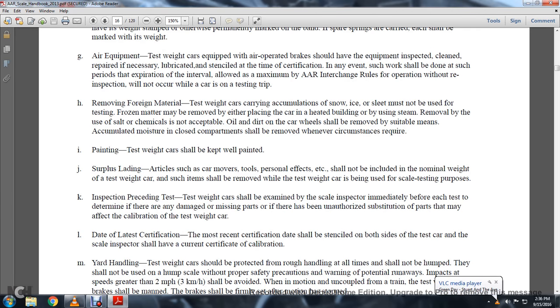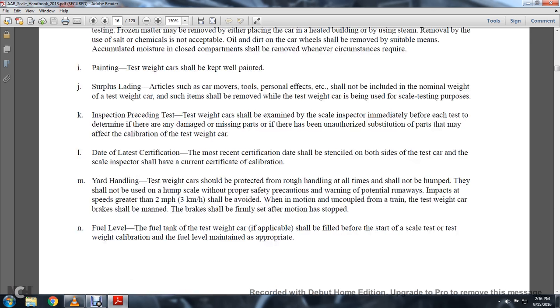K: Inspection preceding test. Test weight cars shall be examined by the scale inspector immediately before each test to determine if there is any damage, missing parts, or unauthorized substitution of parts that may affect the calibration and testing weight of the car. The date of the last certification and most recent certification date should be shown on both sides of the test car, and scale inspectors should have the current certification calibration.